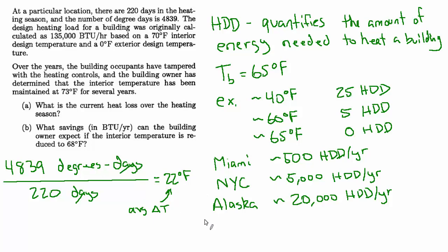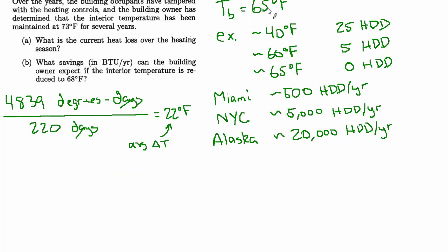Now when we say average delta T, we have to remember that that is referencing the base temperature of 65 degrees and has nothing to do with how the building is actually operated. This is just based on temperature data that's been collected for that area. It's irrelevant to the building design at this point. So we can say T base minus the average outside temperature, which I'll call T sub O, and I'll use this bar to represent average, equals 22 degrees. And we know the base temperature is 65, so we can rearrange this to solve for that average outside temperature. It's going to be 65 minus 22, equals 43 degrees. So the average outside temperature during the heating season for this area is 43 degrees.